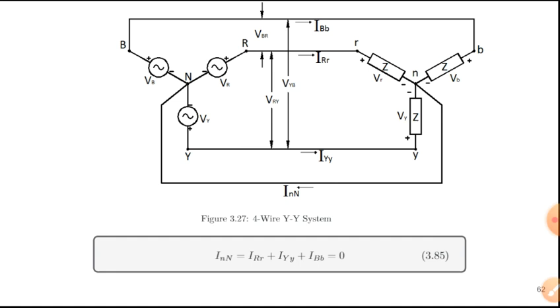Why is the neutral wire critical for unbalanced systems? If there's unbalance on the load, there's an excess current. If there's a neutral line, there's a return path from the load back to the source. But if the neutral line is not present, the current will still flow through the load, causing severe voltage variation — it can be over-voltage or under-voltage. In some loads, voltage is very sensitive; you cannot have over-voltage or under-voltage. So it's safe to use a 4-wire system.